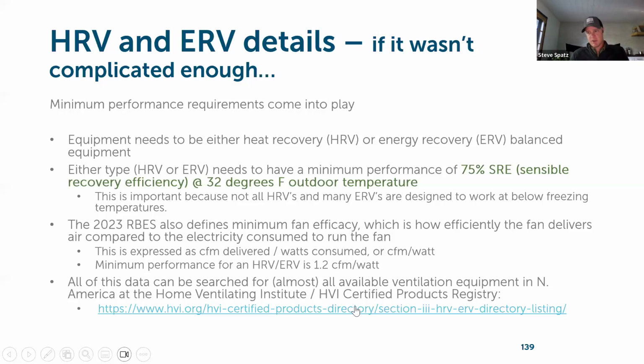There's been a lot of conversation about what's appropriate in our climate. I think a lot of ERVs are being installed, perhaps more than HRVs, because it's important to keep relative humidity in check and not have elevated relative humidity throughout the heating season. But it also is critical that we don't have consistently really low relative humidity, which can create discomfort for the occupants. It can start to affect building materials, and the building can start to shrink and shift and move in ways we don't want. So there's some consideration there between HRV or ERV as you're looking at equipment.